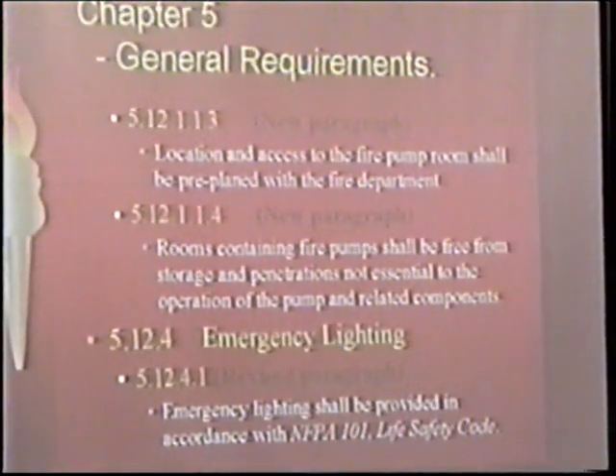These are the new paragraphs in the code book. It talks about rooms containing fire pumps shall be free from storage and penetrations not essential to the operation of a pump and related components. And the storage part of that is probably pretty clear. I'm not exactly sure what the penetrations are that they're talking about. Is that a pipe coming into the pump room? That's our sprinkler pipe. But I think the storage issue is probably a good thing.